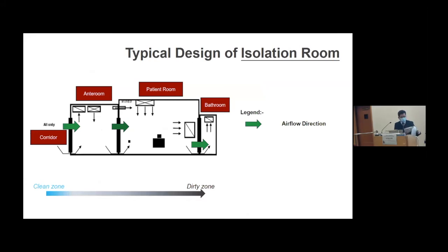Now, this figure shows a typical design of a negative pressure airborne isolation room at hospitals. When you enter the isolation room from the corridor, which we usually call a clean zone, you will pass through the anteroom. The doors of the anteroom are interlocked to ensure the air from the patient's room will not escape directly to the corridor.